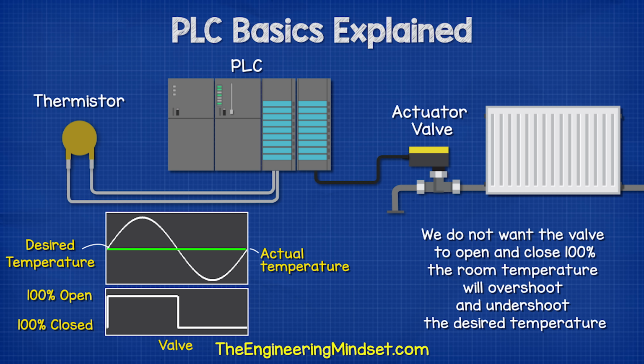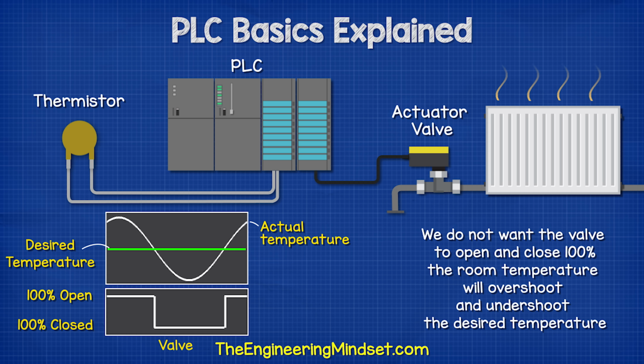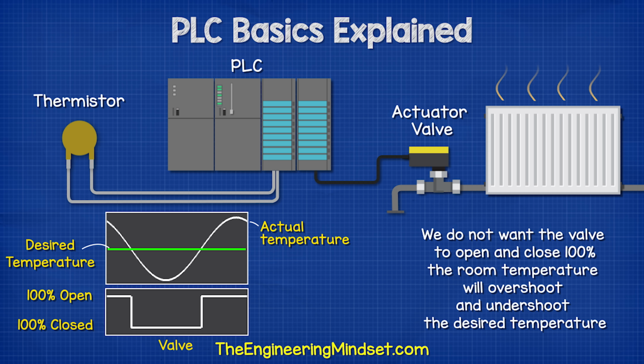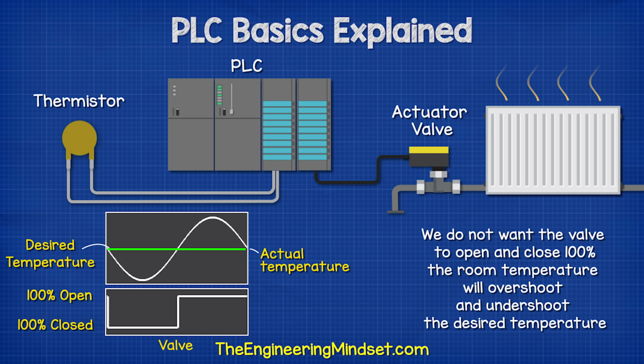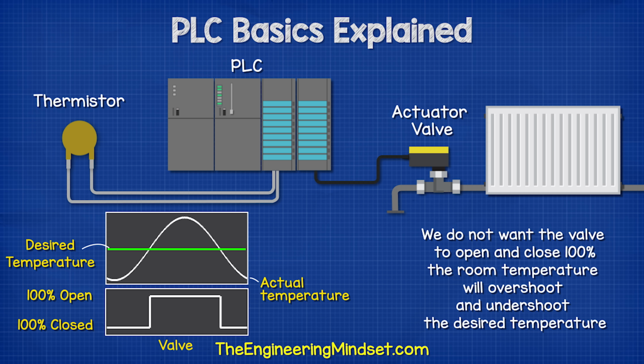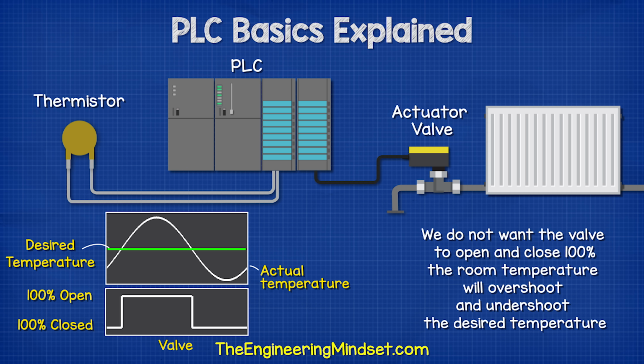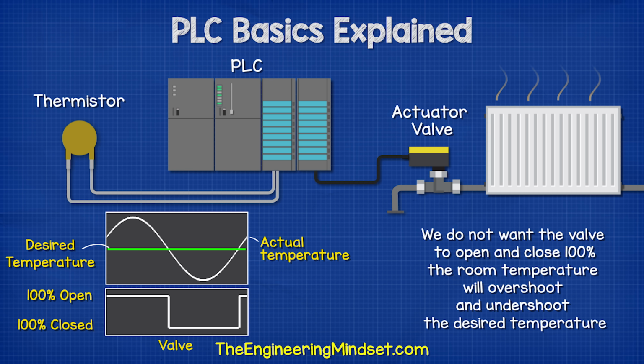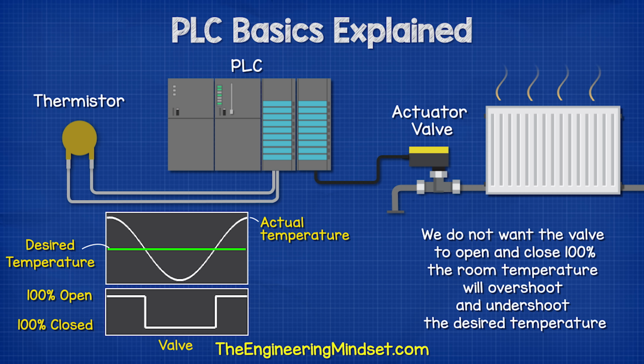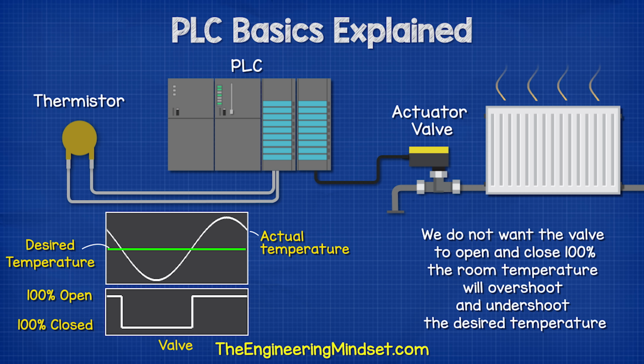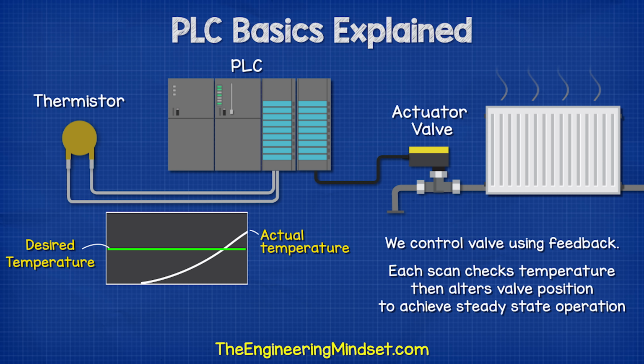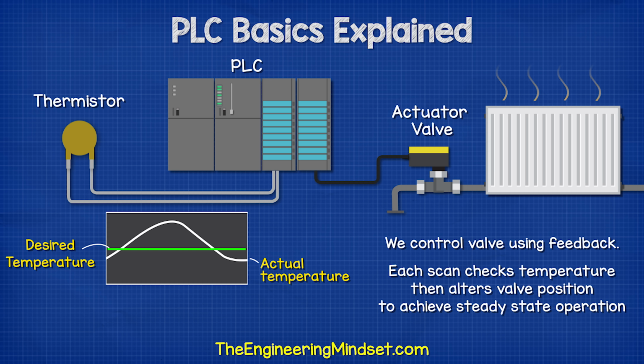For example, if the room temperature dropped very slightly, we don't want the heating valve to instantly open 100%, because the room will heat too quickly and this will overshoot the desired temperature. At this point, it will then instantly turn off and the cycle will repeat. Instead, we want the valve to gradually open in proportion to the demand.